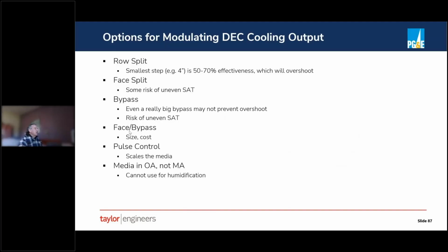You can use face and bypass, basically put a damper in front of the media as well to force more air through the bypass. The issue there is you're going to need to have your bypass full size. So you need more surface area in your air handling system, which can be a challenge.